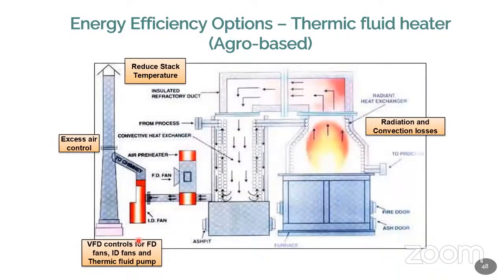Then what are the energy efficiency options for TFH? Sometimes you can also use an agro-based fuel in addition to the oil. That can be used as an alternate fuel. Other things are the same as for the boiler itself. You have radiation loss and conduction loss, which should be minimized by giving very proper insulation. The heated air will go to the chimney, and there you can use a preheater. That preheater can be used to heat up the oil, so that you can reach a very high temperature and similarly very high pressure initially.